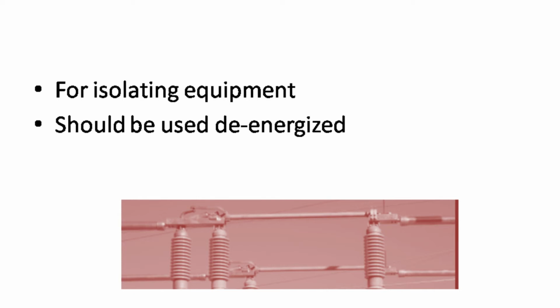In fact, disconnect switches have lockout-tagout procedures in many substations to safeguard the operation of these switches when the circuit is energized. Now, speaking of arc extinguishing capability, some may actually have arcing horns that stretch the arc until it cannot sustain itself, whereas some are equipped with a whip to extinguish the arc, and some others have switch contacts immersed in oil that quenches the arc.